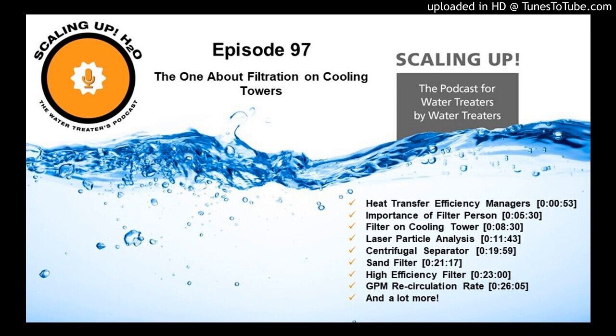What is that process? Well, I think it depends on what filter company you represent. Everybody's got their own point of view on this. People like me have always worked with high efficiency filtration, which is filtration of 5 micron and smaller particulate, because of the belief by people like me that the really fine particles are what cause the problems in cooling water systems. And that's what most of the particulate is. When you do a particle analysis, you'll see there are millions of particles in the 0.5 micron to 2 micron range, and maybe thousands or hundreds in the 25 micron range. So the particles that are larger than 10 microns or so don't float around in the water much. They settle in the sump.